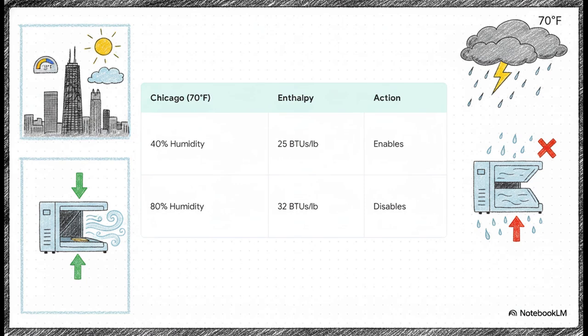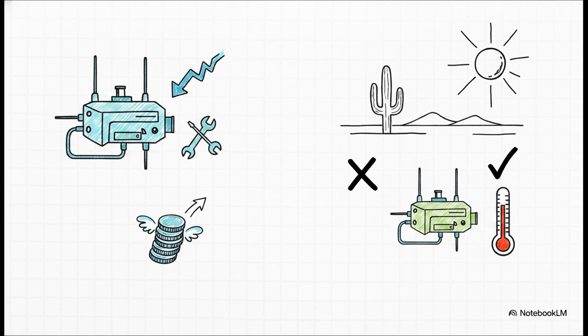Let's imagine a hospital in Chicago to see this in action. Say it's 70 degrees outside. If the relative humidity is a nice, comfortable 40%, the total enthalpy is only 25 BTUs per pound. That is well below our 28 BTU limit, so the Economizer enables and pulls in that sweet, free cooling. But let's say a storm rolls in. The humidity spikes to 80% at that exact same 70-degree temperature. The enthalpy jumps up to 32 BTUs. Boom. The system is smart enough to immediately disable those dampers, blocking all that excess moisture from getting into the hospital. But yeah, there's always a but, right?